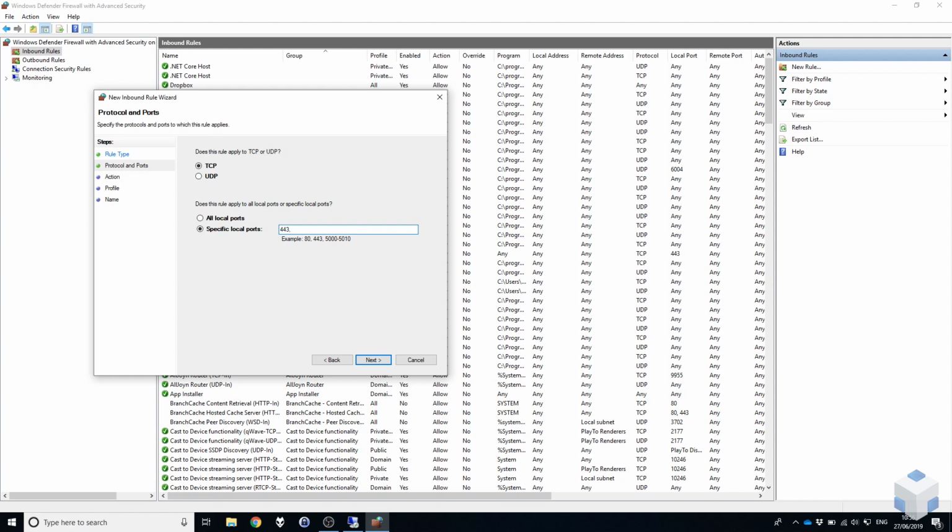The next port is 4911 TCP. Now this is for Fox S communication, which again is the default secure Fox communication protocol for connecting to your station via Workbench and via the Niagara network from other Niagara stations. The last one is 5011 TCP. This is the secure platform connection.